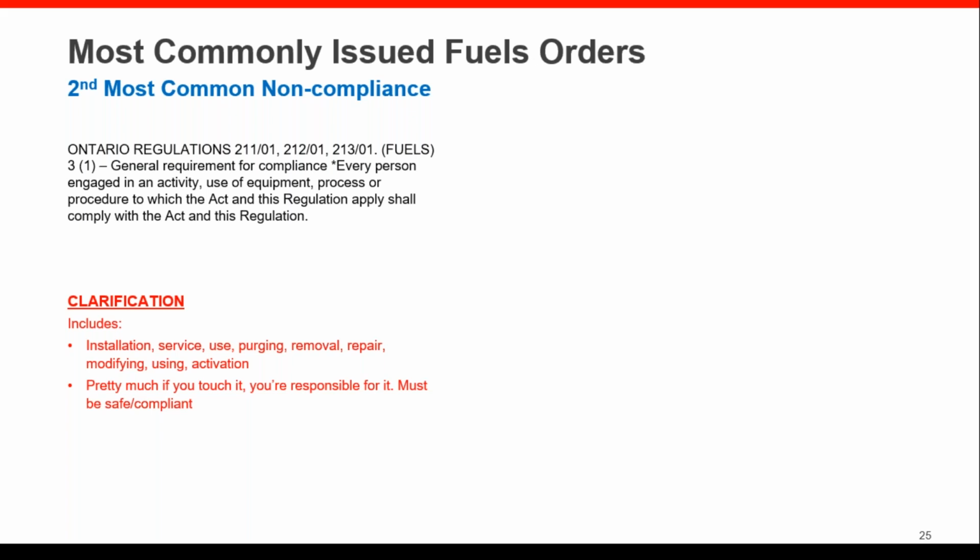And when I say that, I mean you're responsible when you leave to make sure it's either safe to operate, or you shut it off, or it's compliant, and if it's not, you have to tag it. You have to red tag it, inform your customers that there are things to be done, especially if they're not going to allow you to make that repair on the spot. But if you're not repairing it then and there, then you need to tag it and follow that process that we have in place.